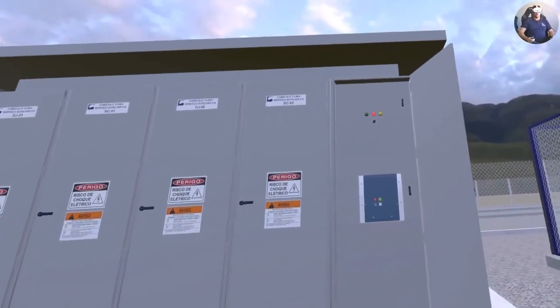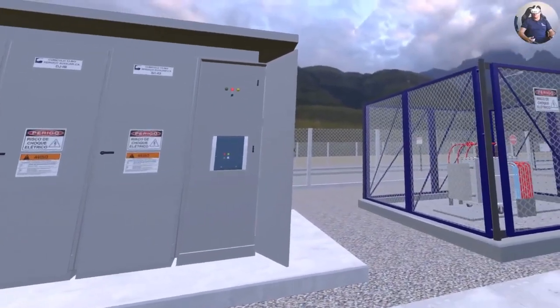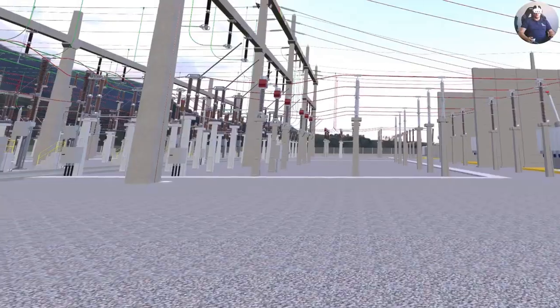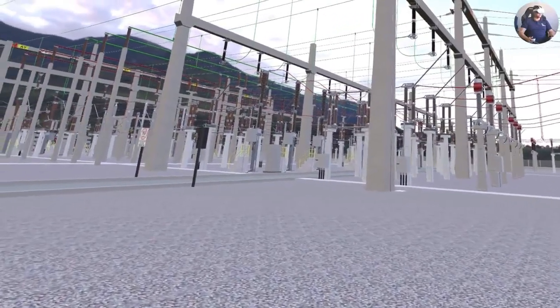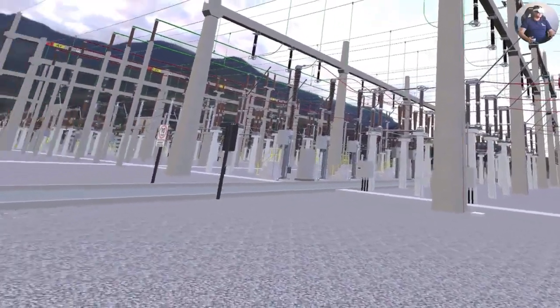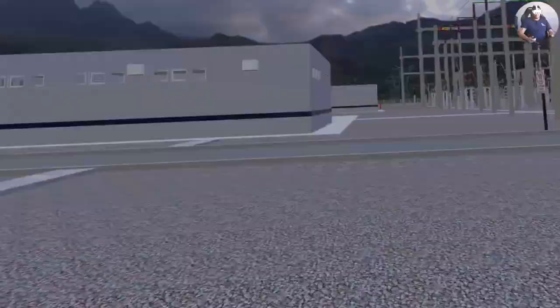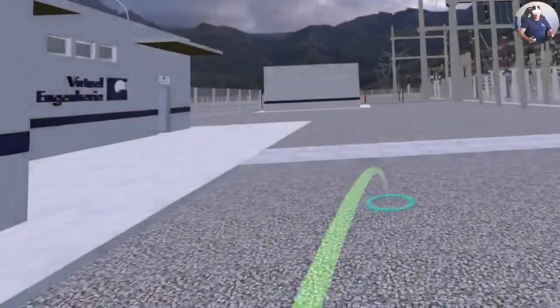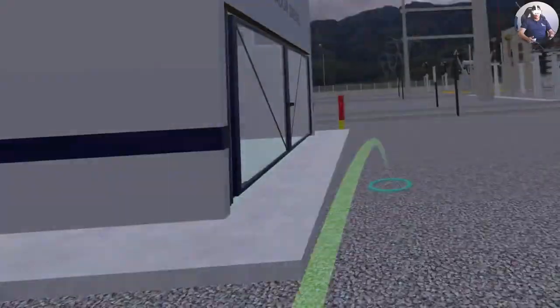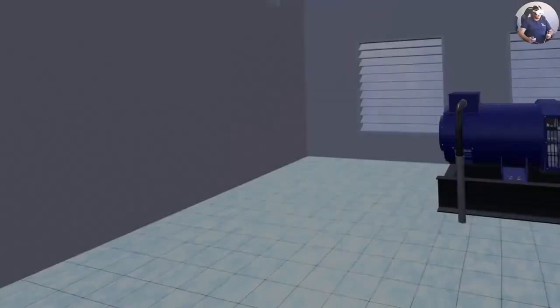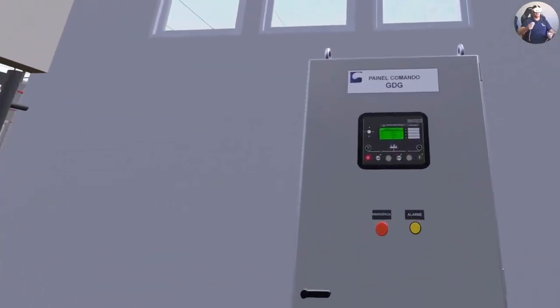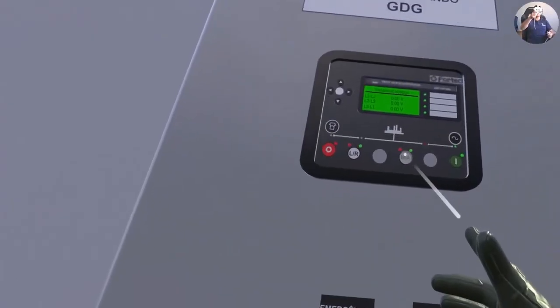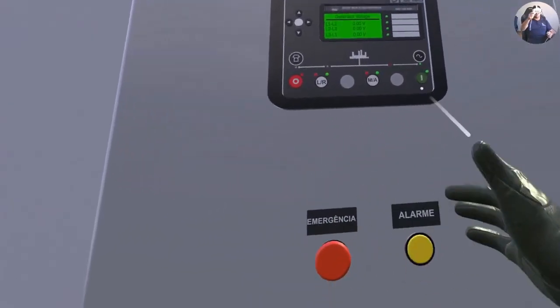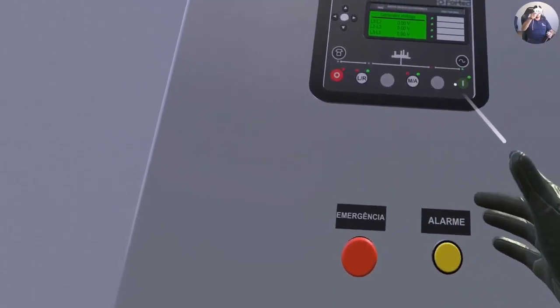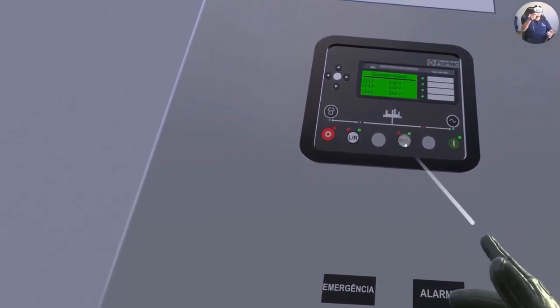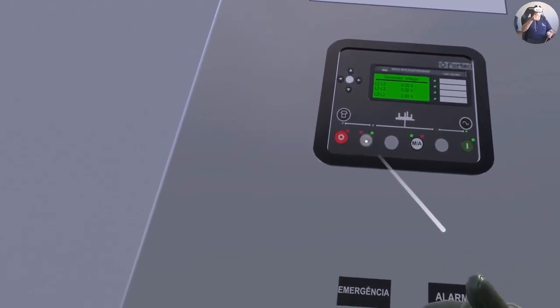We're back now with the transmission transformation function together with the auxiliary service. So the substation is now operating once again here with the function in place. Transmission transformation AT2. So we went there, switched the diesel group to manual and local, guys. I'm going to switch back to remote and automatic. And I called the maintenance team to see what happened here since the GDG started, right? So here, guys, I can perform commands manually, right? So if I give a command here to turn it on here, I can do it, right? So I'm going to switch here then to automatic and remote.